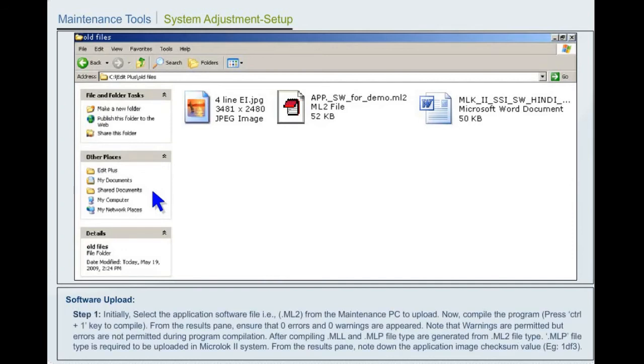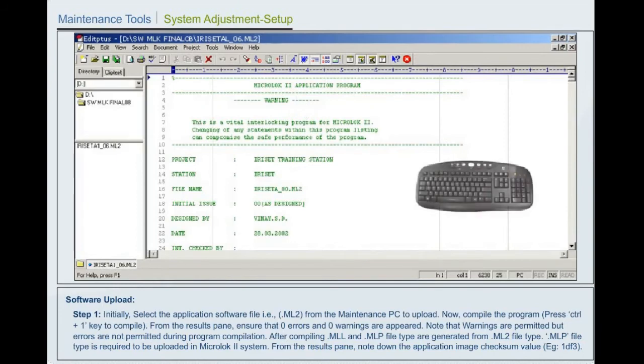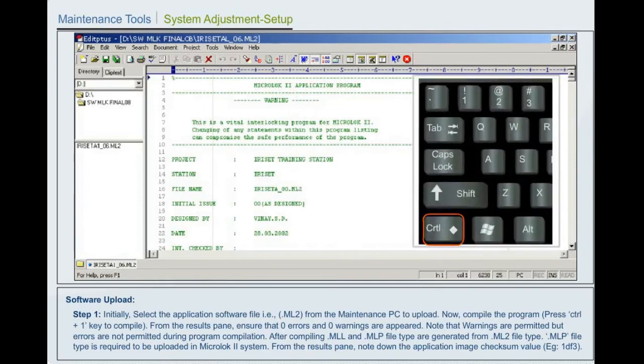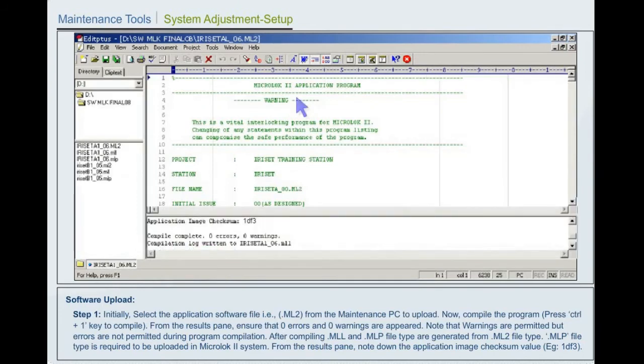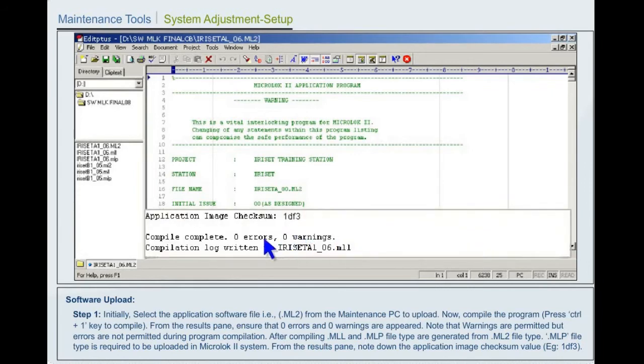Step 1. Initially, select the application software file, i.e. the .ML2 file, from the maintenance PC to upload. Now compile the program. Press Ctrl+1 keys to compile. From the results pane, ensure that 0 errors and 0 warnings have appeared. Note that warnings are permitted, but errors are not permitted during program compilation.